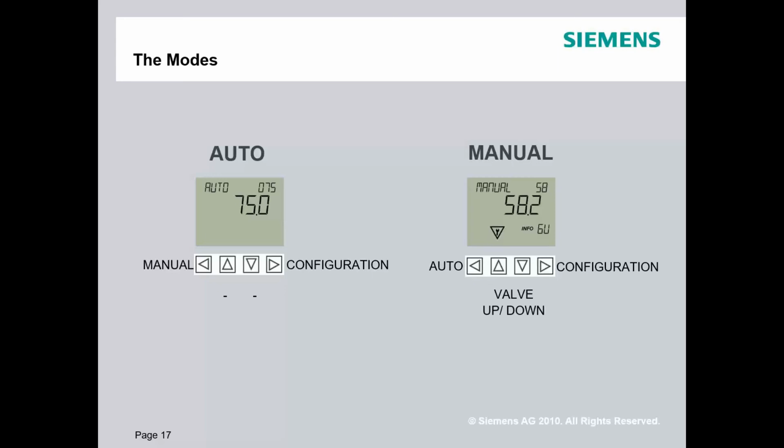And the beauty of it is that if I go from manual back to automatic, it picks up. It just goes. I don't have to reset anything. I don't have to tell it anything. The signal can be changing. It'll jump right on that signal and start following. There's not any adjustment here. That's what I like. I calibrate it, I put it in service, and I don't have to go back unless I just want to.